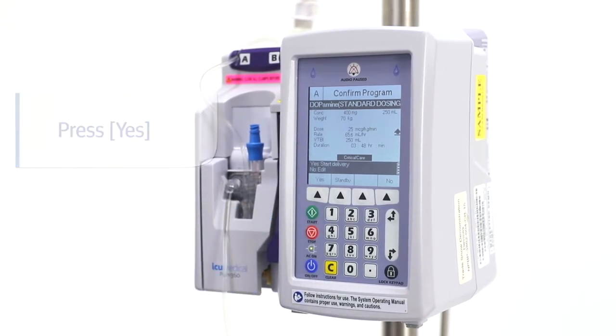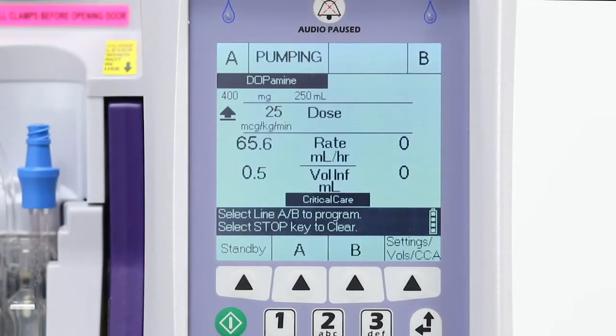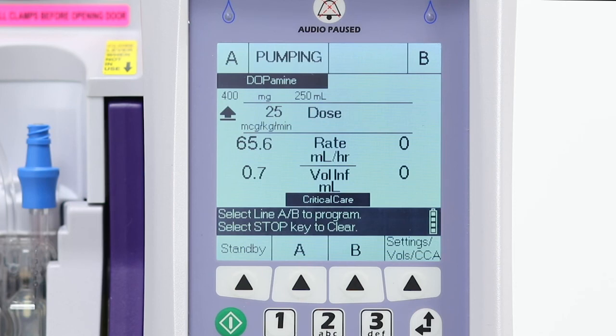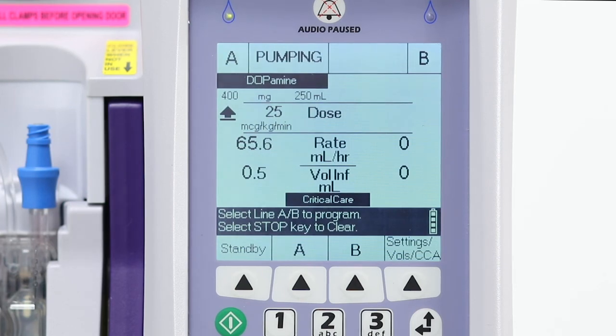The infusion will start, and the status of line A shows pumping. The flow indicator is flashing green, while the main delivery screen will display the drug name, dose, and rate. Also displaying on the delivery screen is the soft limit override symbol indicating the programmed soft limit, upper or lower, has been overridden.